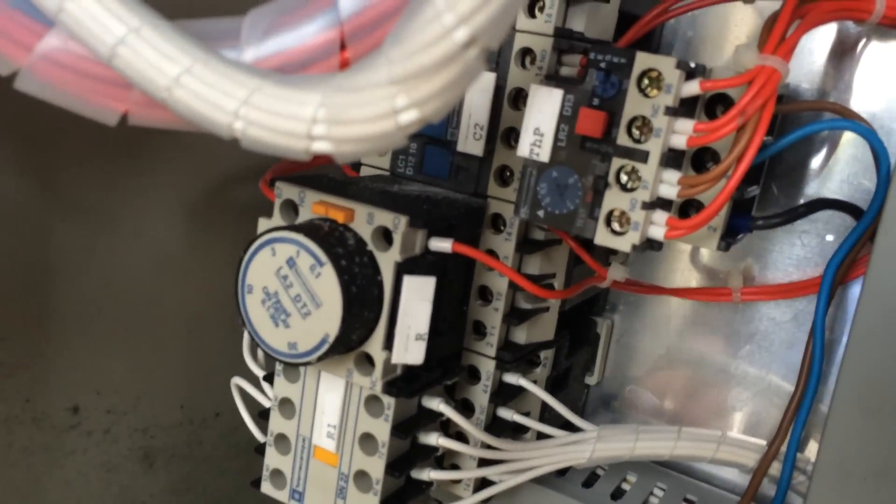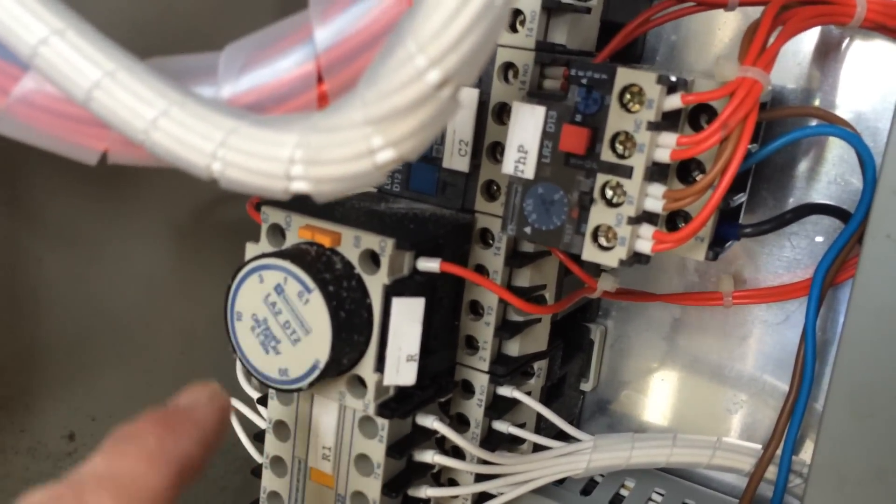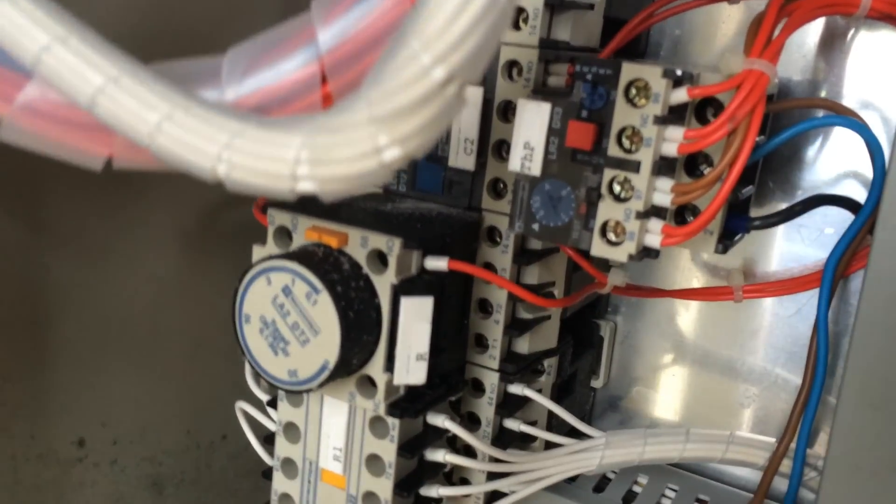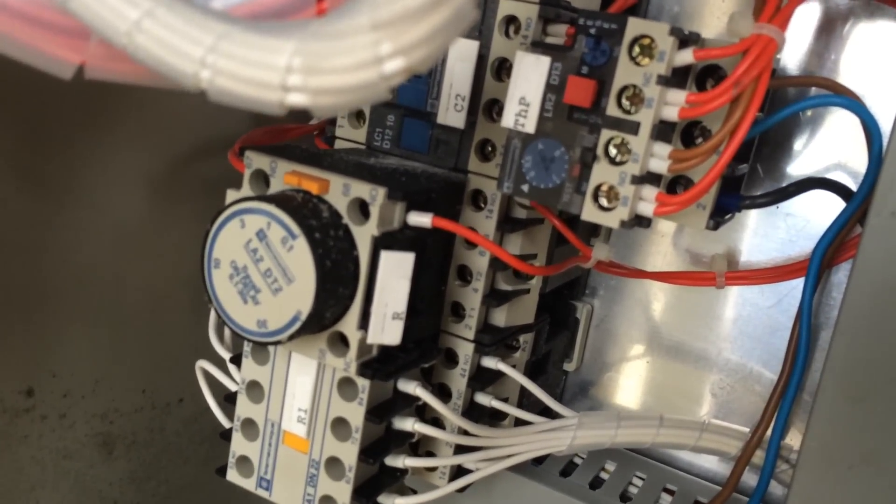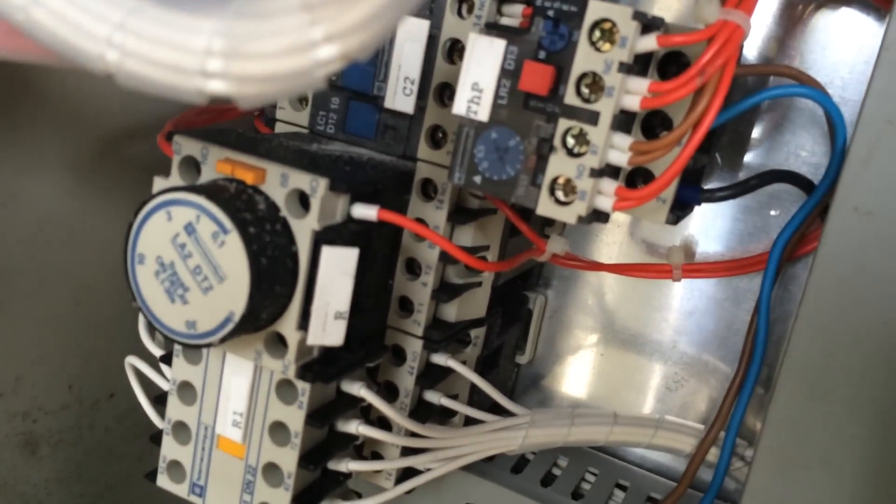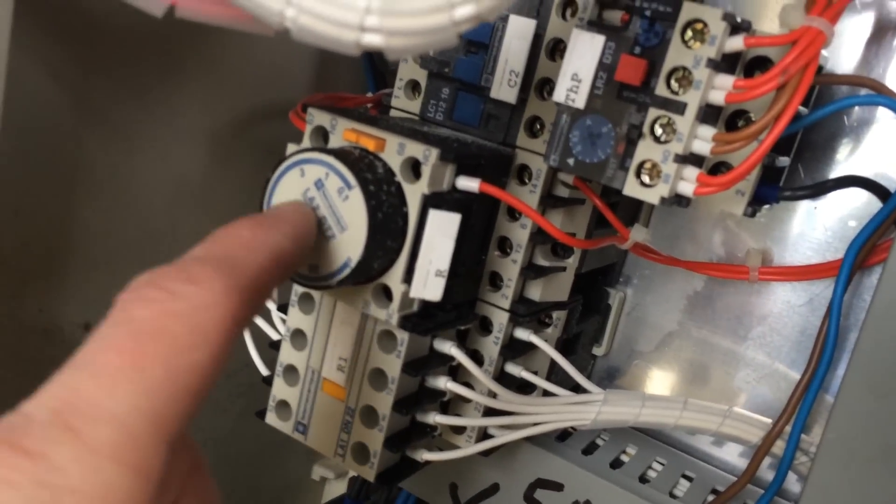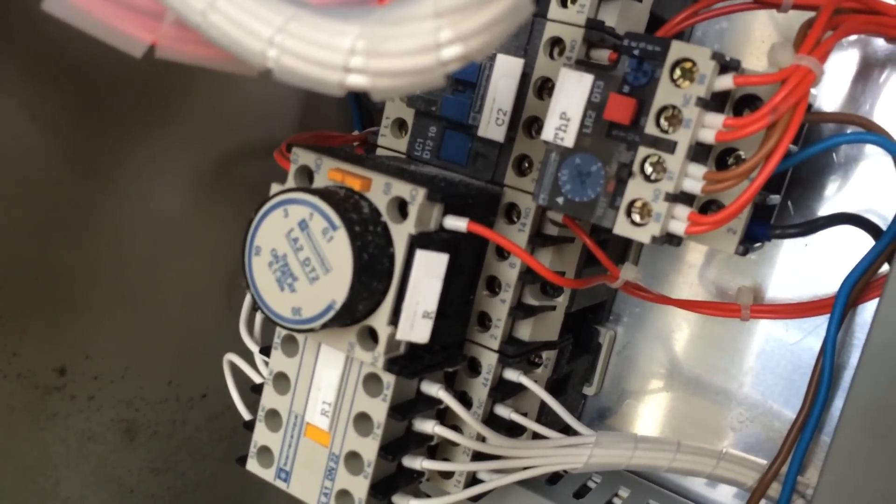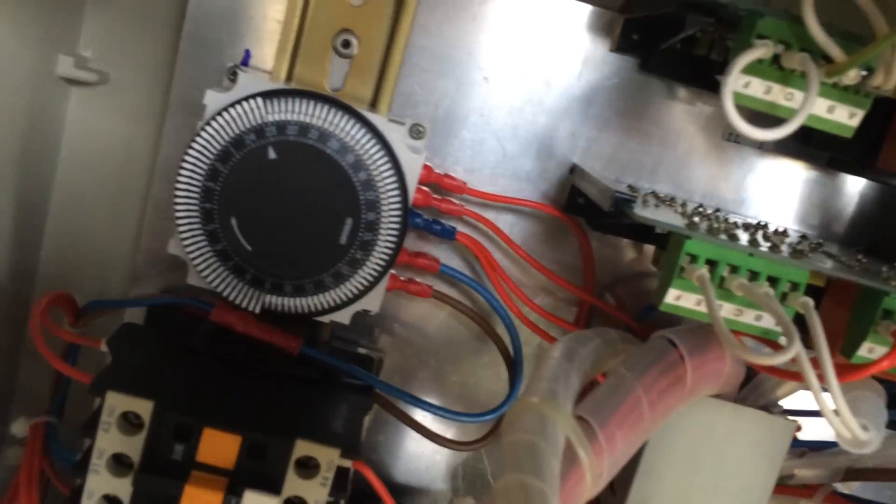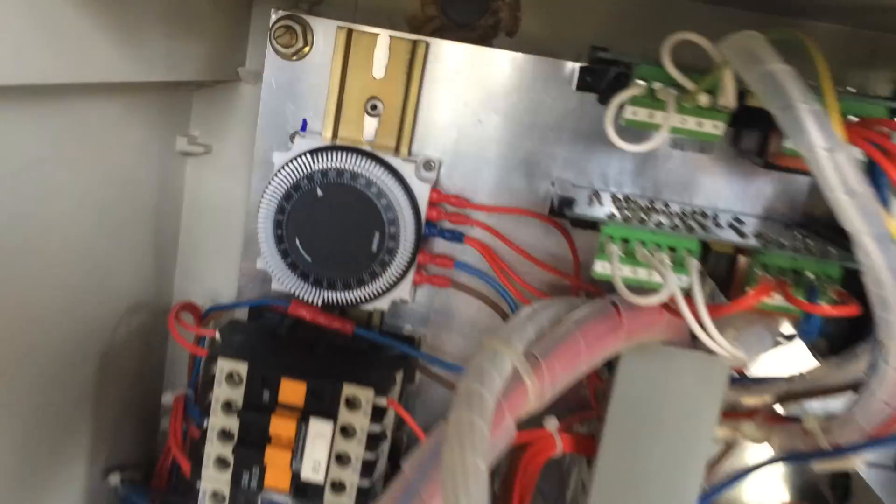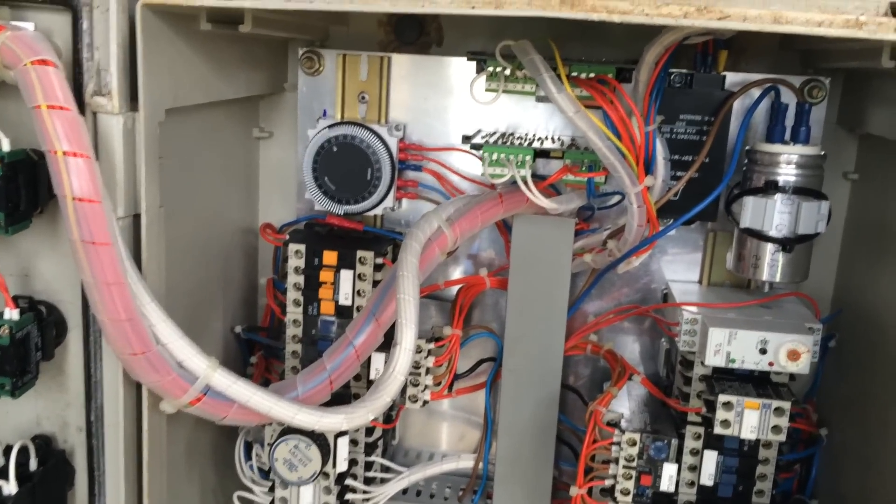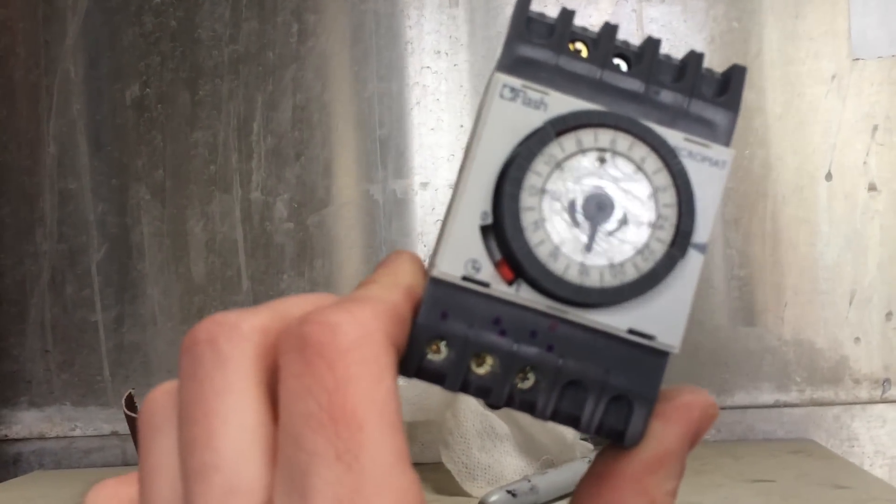I'll need to check the wiring diagram to see how exactly that's done, but I've got a suspicion that it's run off of that wire there. Which I think is the second solenoid. There we go. Which I think is the second ice pack control, which is the second solenoid. You just hear a click. And that's the job done. That's the old one. It's probably original.